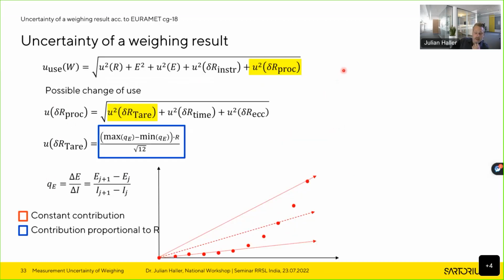The next part actually is possible change of use. As mentioned, during the calibration you do not use the tare function, but the user might use the tare function of a balance. And this is of course again a very extreme example, but if you have a strong nonlinearity of the errors over the weighing range, then if you imagine taring would have an effect, the determined measurement uncertainty for the net weight is not correct anymore. And therefore, an assumption or approximation of possible effects of the tare function is made. Again, some rather complicated formula which uses the maximum slope of the error of indication and then assumes a worst case scenario for taring the balance.